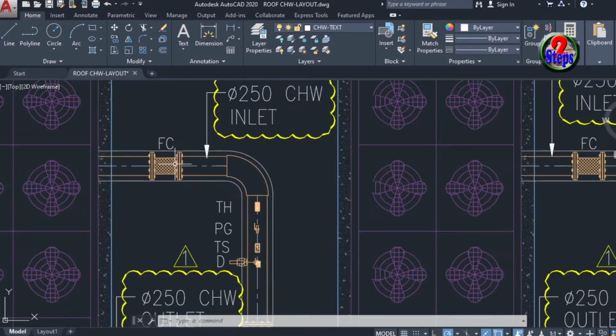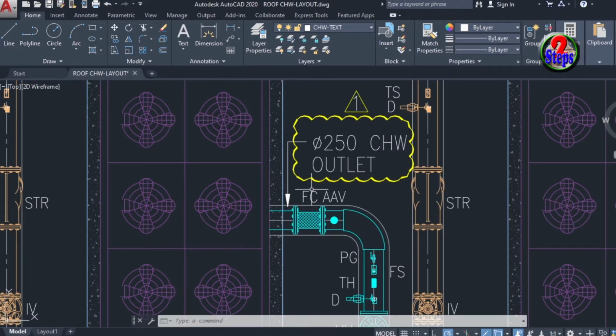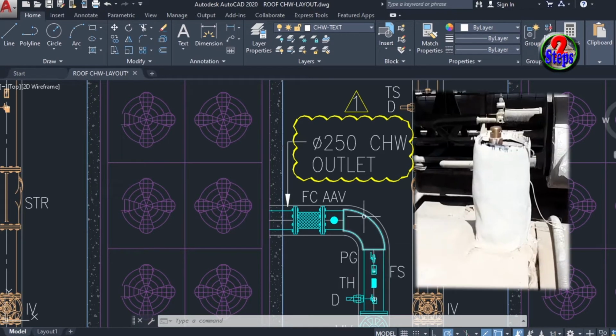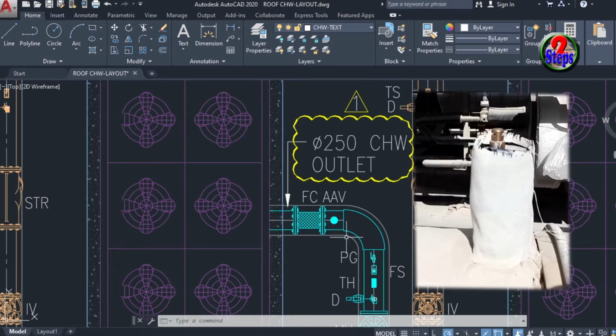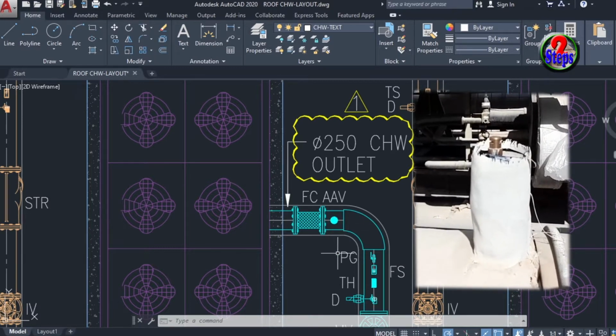Same as the inlet pipe, the outlet pipe also has a flexible connector. After that, there is one point for the automatic air vent. The drawing symbol is AAV. Sometimes it is written only as AV. If there are any air bubbles inside the pipe, it will ventilate them.